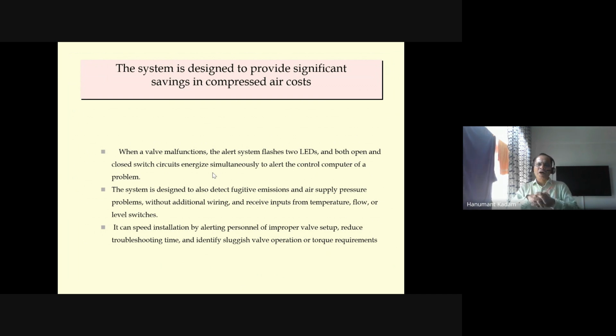When a valve malfunctions, the alert system flashes two LEDs. There are two LED indicators on the valve. Both open and close switch circuits energize simultaneously to alert the control computer to a problem. So in the control system DCS, you will get an alarm. The system is designed to also detect fugitive emissions and air supply pressure problems without additional wiring.